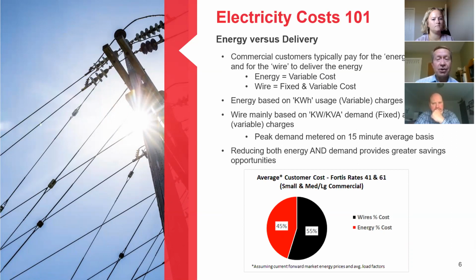So energy charges are based on the kilowatt hours that you consume in a month. That's a variable charge, because you can use different volumes of kilowatt hours in any given month. While the wires or the delivery charges are based on both the variable kilowatt hours and the peak demand, which is more of a fixed charge, and that's typically measured in kilowatts or what they call KVA or kilovolt amperes.